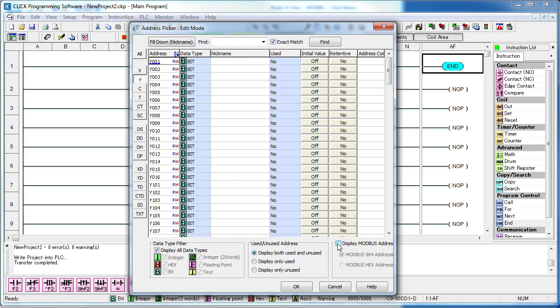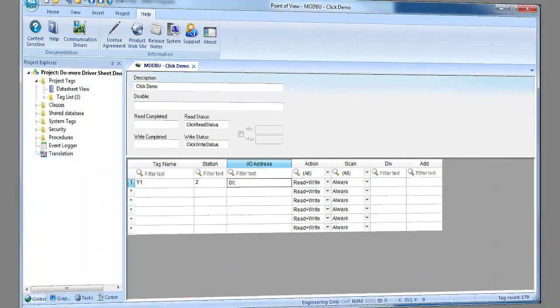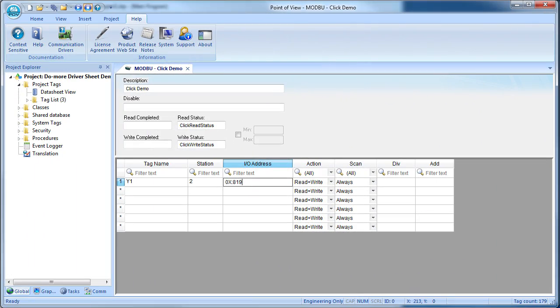Click on this little checkbox and the Click software tells you exactly what the Modbus address of that memory location is and which function codes can be used with that address. Looks like Y1's Modbus address is 8193, so back in the driver sheet we put that here.